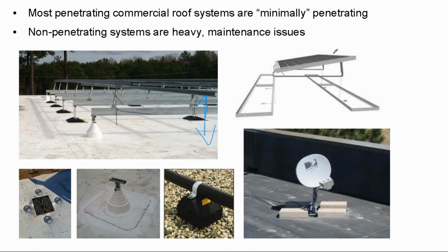And so there's a couple of problems. There's a cable management problem where these solar cables need to hop from one row to the next, and then they also need to hop from one row to the next row. And so if you don't have any mind to cable management, you're asking for that circuit underneath the module to be dragged underneath this panel, which again is only going to be an inch or so up off the rooftop.